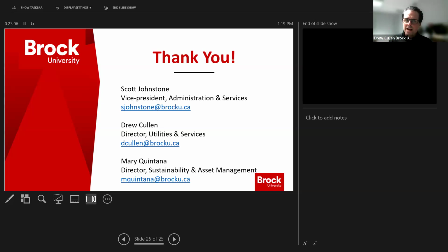We have 2 feeders on our campus. In the event of a power interruption on our main feeder, the campus will switch non-critical buildings to the second feeder. However, our lab research-intensive and science buildings with all the expensive equipment do not like power interruption, no delays. So we island the plant to have no interruption for those buildings. The campus critical load is over 2 megawatts, so we run 2 engines all the time.